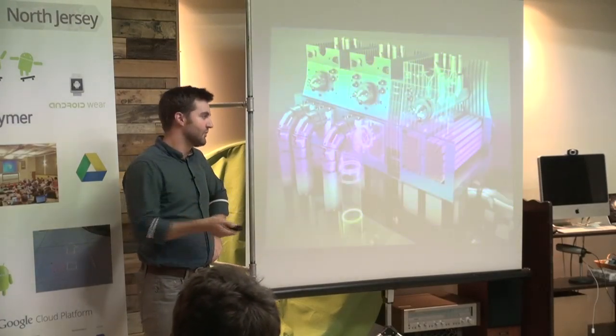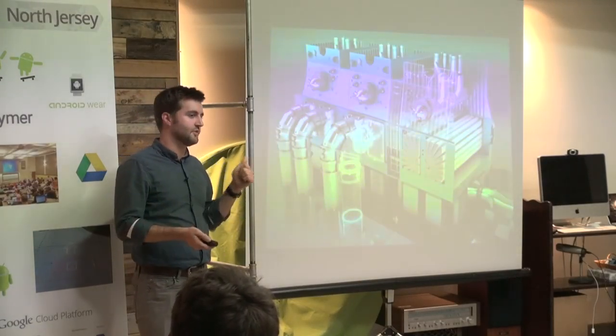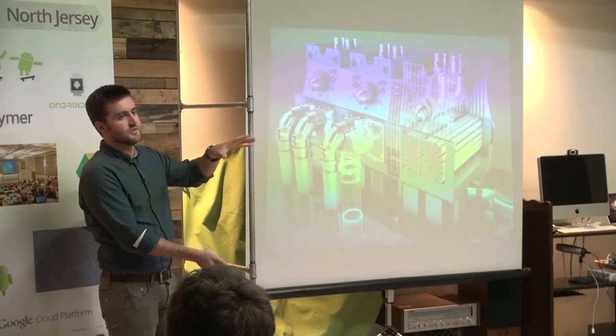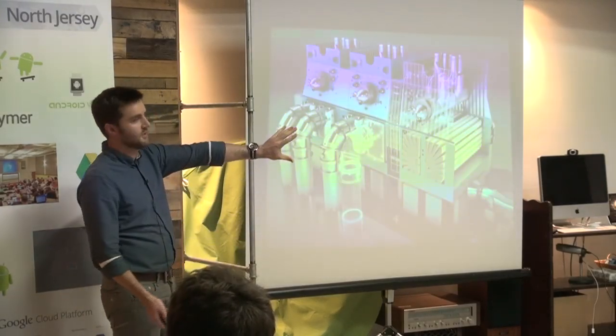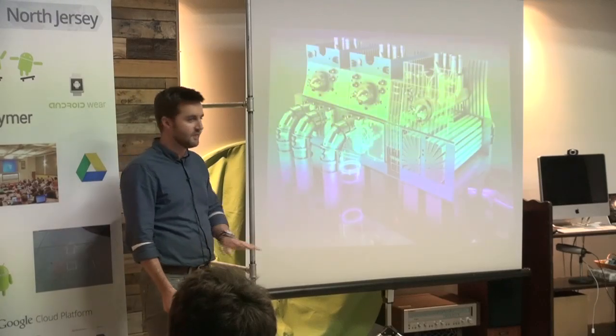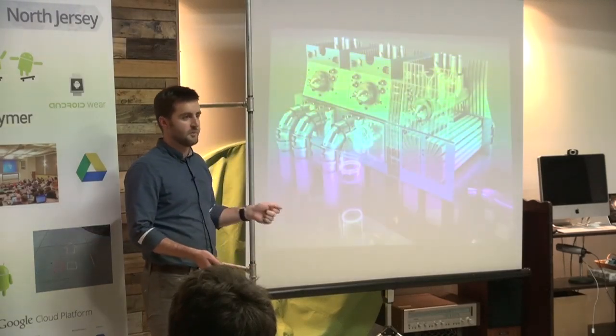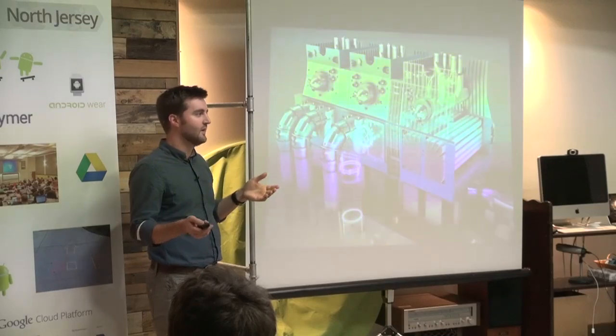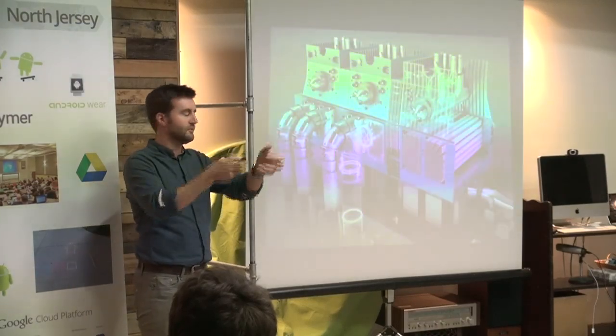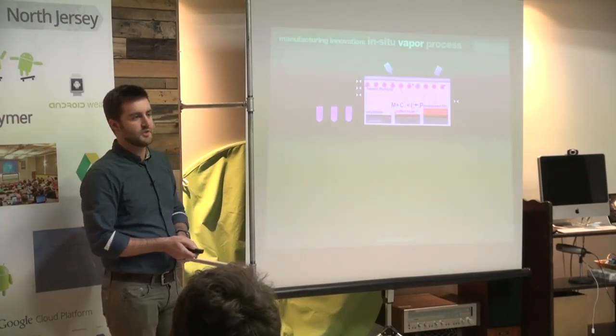Within the last six months, we finally invented a way to solve the last and most challenging problem — how to get the coating on all these tubes. The condenser is enormous; it has hundreds of miles of tubes. All previous technologies have failed here because everyone's tried liquid-based coatings, which are either too expensive, too slow, or too thick. You can't use pre-coated tube swaps — coating 10,000 to 20,000 tubes takes several weeks, but plants are only down for a week. Spraying never gets thin enough. Flooding the condenser requires half a million gallons of liquid. None of these work.